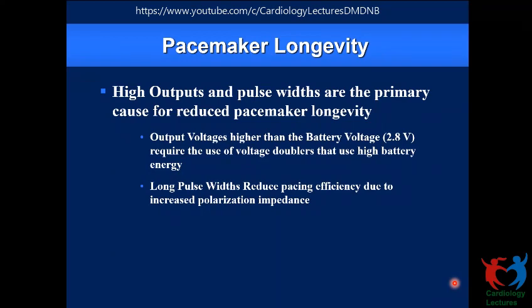So when a patient comes after implantation and also for a follow-up, we check the output, we check the voltage threshold, and you want to build a bit of a safety margin. Usually it's a twofold safety margin. Let's say if your voltage threshold is 1 volt, then you ideally want to program an output of 2 volts, so that even if there is a change in the thresholds, there is a reasonable safety margin already built into our output. But while you're programming, the reference point should ideally be the one which refers to the least energy outgo. You check the threshold at 0.4 milliseconds, let us say, and you get a voltage threshold of 1 volt. For the same case, you make the pulse width 0.6 milliseconds and check the threshold. It will be less than 1 volt. Let's say it becomes 0.7 volts.